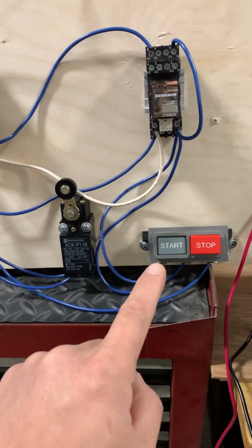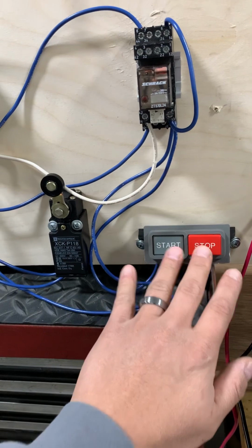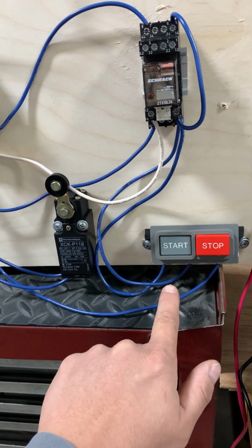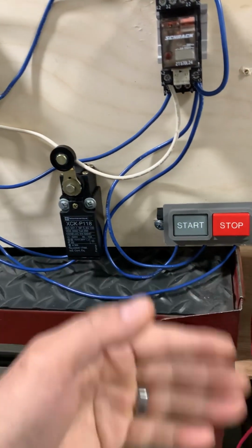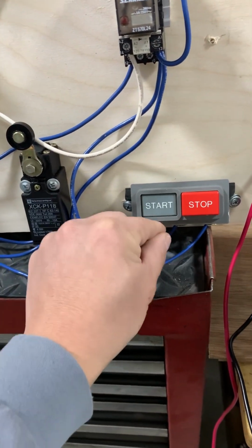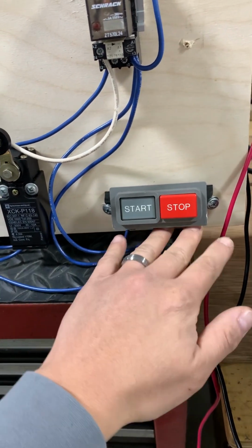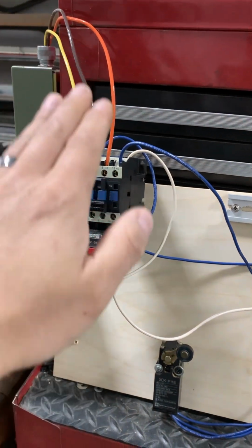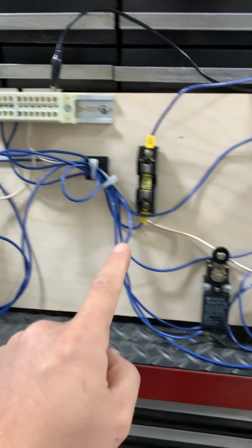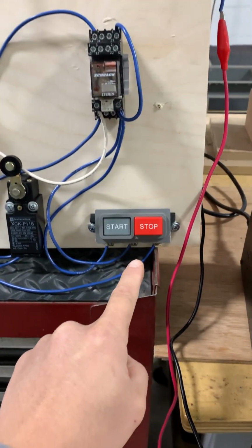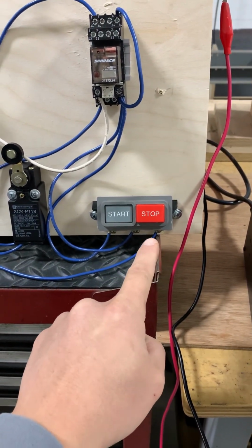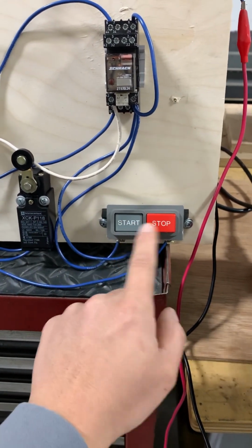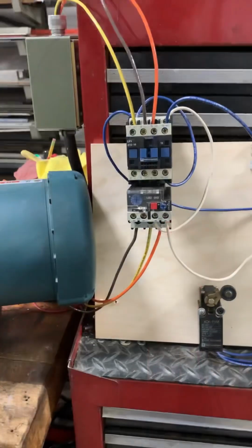The low voltage is much safer because the components that the operator will need to come and touch are running off 24 volts DC. So if anything would happen, a wire would fall out and an operator would accidentally touch it, they wouldn't even notice it. Compared to if everything here ran off 480 three-phase, the operator will not be as lucky if they would accidentally touch a wire that fell out from the electrical components that they need to touch and operate.